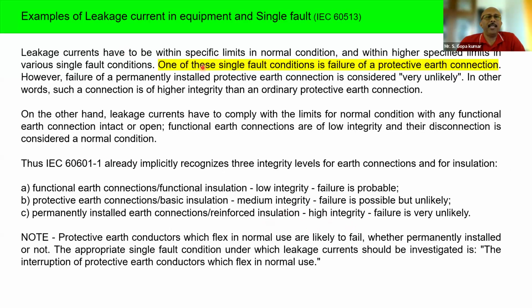Similarly, if you look at these standards, in different places you can see the single fault condition is explained. The single fault condition means, for example, a protective conductor. You see, one of the single fault conditions is failure of a protective earth connection. As you are aware, protective earth connection means you have an equipotential bonding zone within the medical location, and the protective earth conductors must be connected to a common bonding bar. These are very well there in the standard. You can refer to it later.